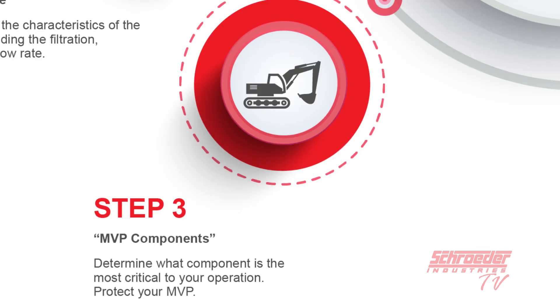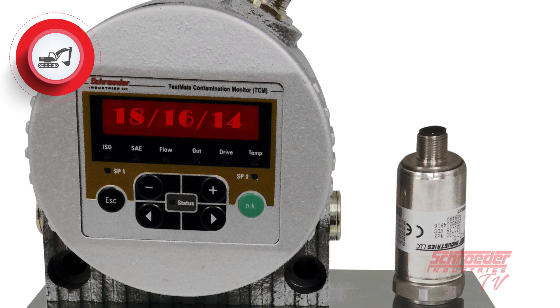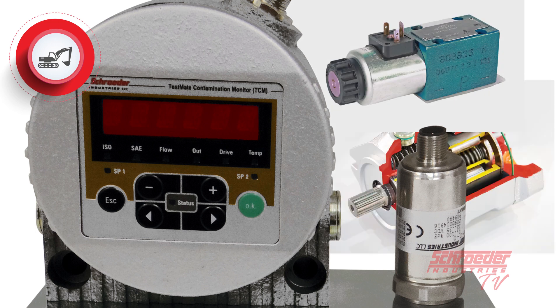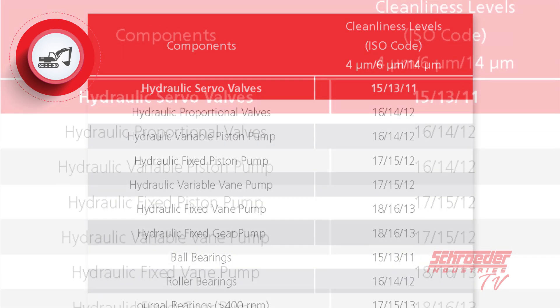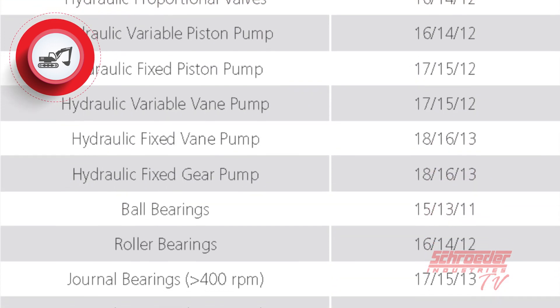Step three is to figure out what your most valuable component is — that is, what component in your system requires the lowest or cleanest ISO code reading. It never hurts to pick an ISO code that is lower than the smallest ISO code that you need. If you're unsure about what ISO code you need, think of components that are breaking down or wearing out the fastest. As a note, we have charts available for general component ISO code levels for just about any part you are looking for.